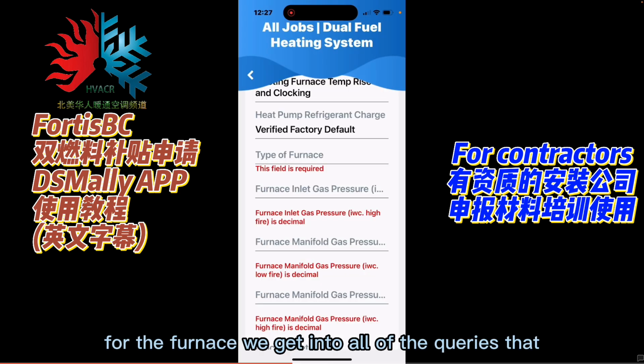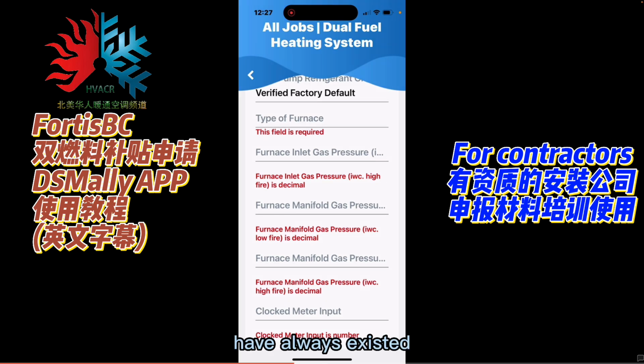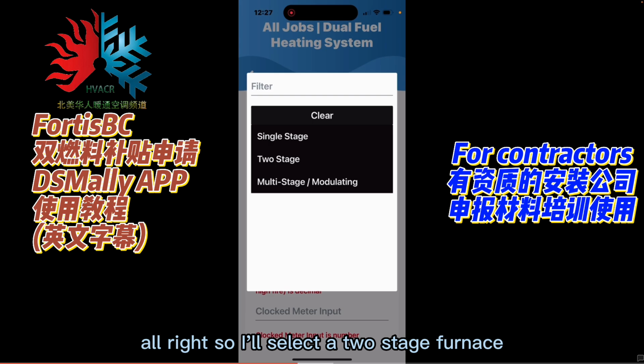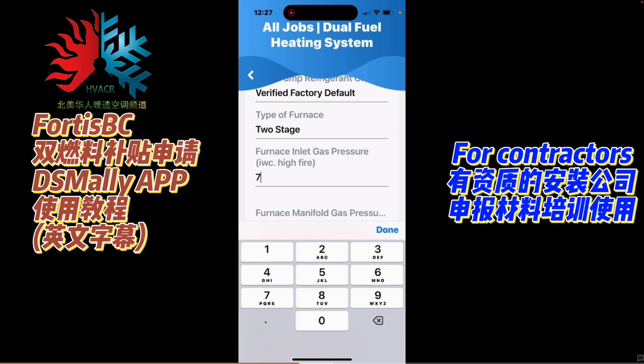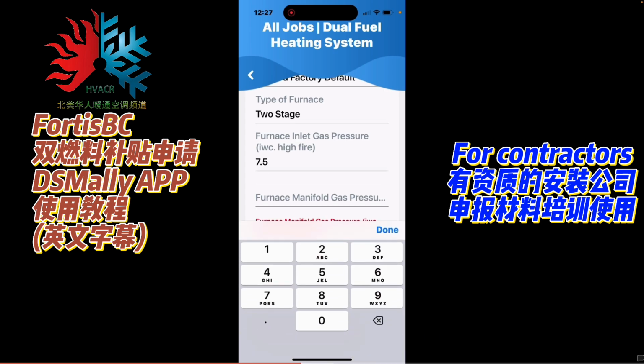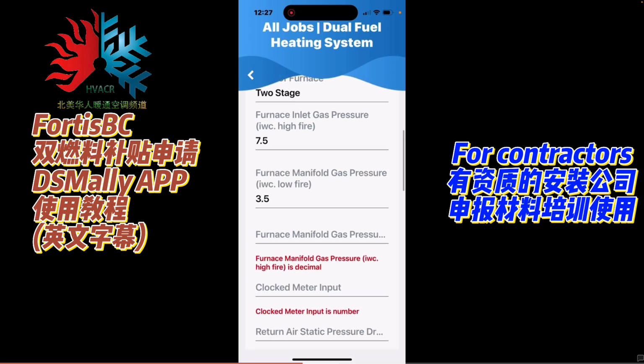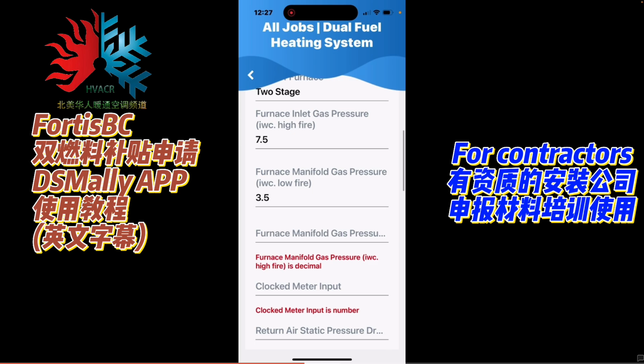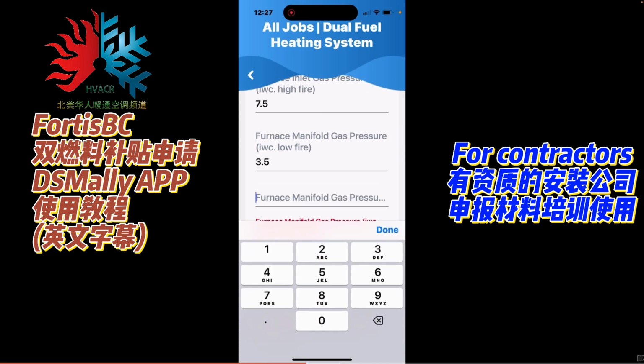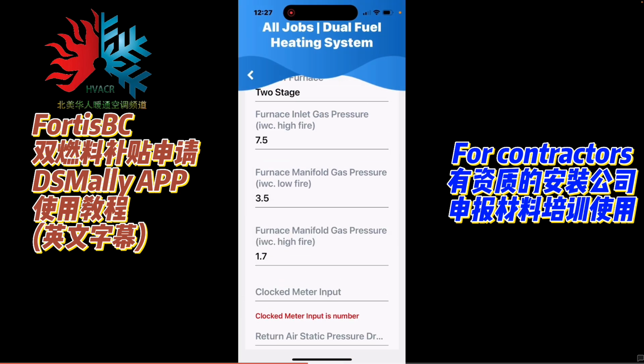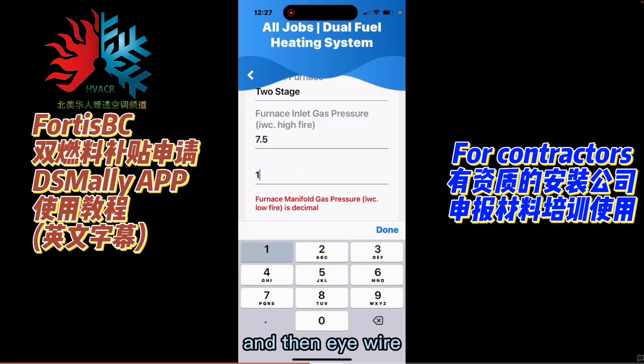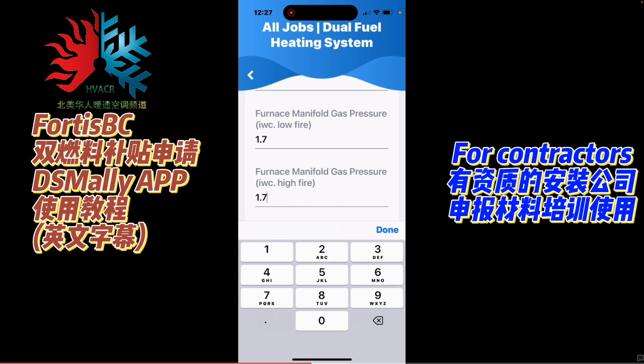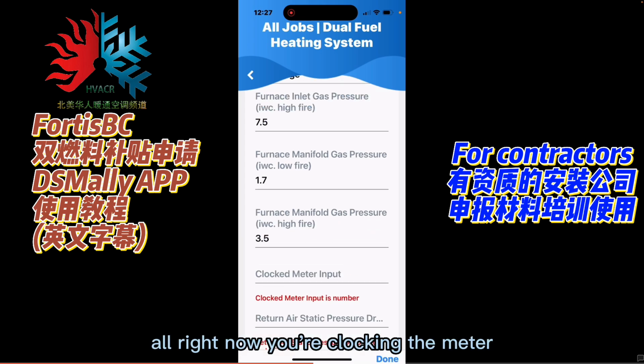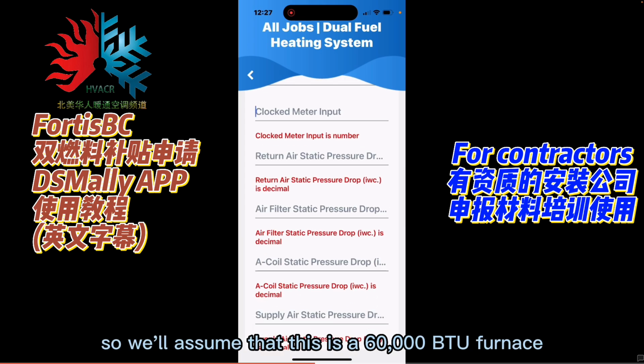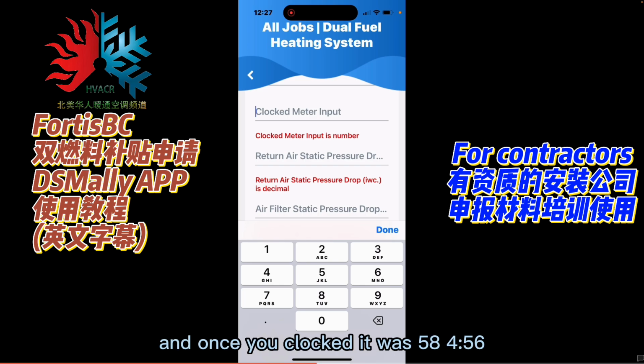For the furnace, we get into all of the queries that have always existed for the furnace programs, all right? So I'll select a 2-stage furnace: inlet gas pressure, manifold pressure, high fire. I'm sorry, it's low fire first, and then high fire. All right, now you're clocking the meter, so we'll assume that this is a 60,000 BTU furnace, and once you clocked it, it was 58,456.